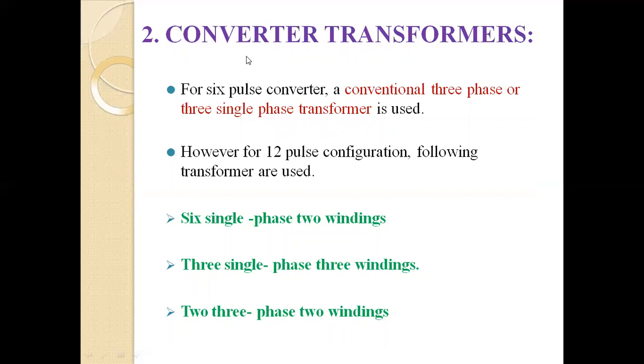Second part is the converter transformer. For a 6 pulse converter, a conventional 3-phase or 3 single-phase transformer is used. However, for the 12 pulse configuration, the following transformers are used. First, 6 single-phase 2 winding. Second, 3 single-phase 3 winding. And third is 2 three-phase 2 winding.